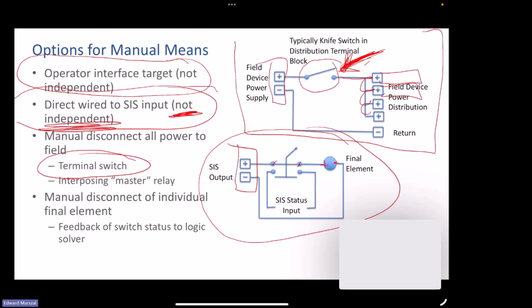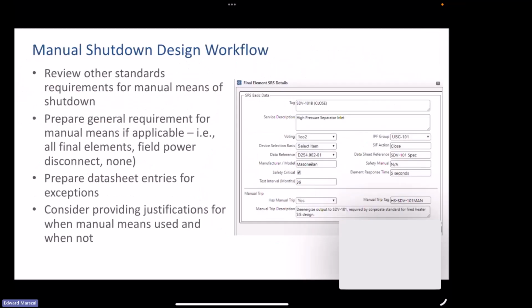So what we would recommend, if you have an infinite amount of money and you want to do this elegantly, is a 2-position selector switch. Right now it's in the normal position. And then there's going to be another position, which is, let's just call that the shutdown position. In the shutdown position, which is going to be kind of the red lines, the top switch becomes open where you disconnect the power to the field.